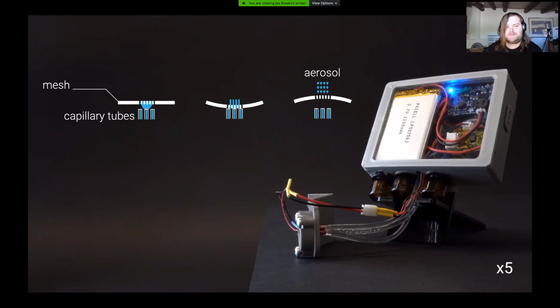Second, because we're only using one atomizer and we have multiple channels of liquids, in this case 3, it becomes paramount to try and reduce cross-contamination. In other words, we just want the selected channel to be outputted. So to try and avoid this, we made sure that each of the channels had their own separate reservoir, set of tubing, and micropump. On top of that, we added something called a capillary tube to the end of each channel. What this does is constrict the flow a lot so that there's a high surface tension in the liquid. And when the micropump creates a droplet, the droplet gets picked up really quickly by the vibrating mesh transducer and gets aerosolized. On top of that, when you have these capillary tubes, it's really hard for backflow to happen. So if one channel outputs and then it covers another channel, it doesn't flow back into the channel's tubing. This means that we can only do mixture at the point of atomization and further reduce any potential cross-contamination.